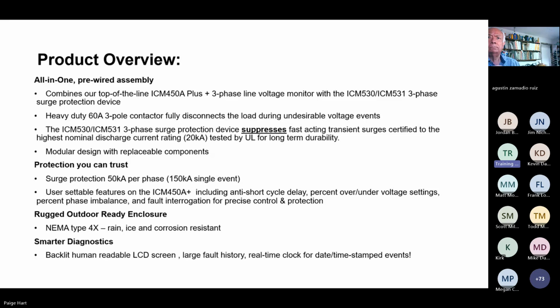User settable features on the 450A Plus include, for example, anti-short cycling. The anti-short cycle delay will help prevent short cycle events. This is all included in our voltage monitor, so in case the power is going in and out and things are shutting on and off too quickly, the ICM will not allow the contactor to close until the delay period is over with. You also have things like percent over and under voltage that are user settable, percent phase unbalance for precision adjustments to any application you have. There's also a great feature called fault interrogation for non-critical faults, so you don't get a lot of nuisance trips, okay?